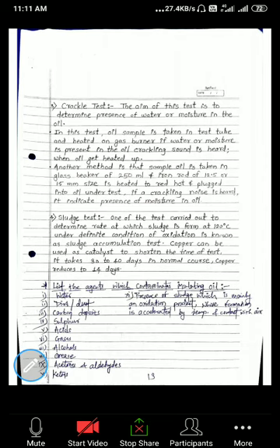You have to heat the oil in a test tube till you hear a crackling sound. If a crackling sound is heard, definitely you can say that the oil contains water or moisture content.